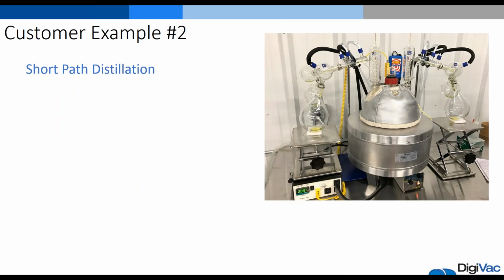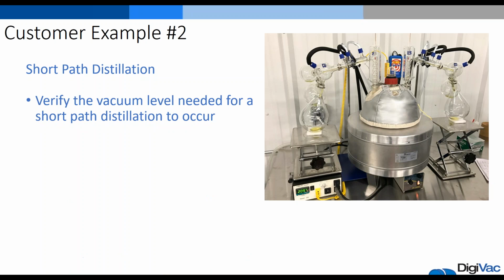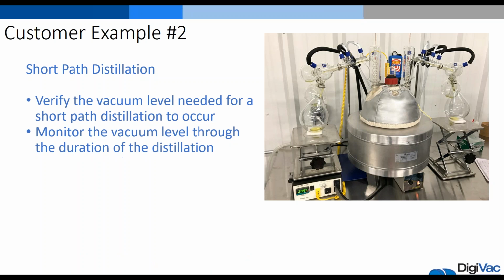Another customer example would be short path distillation, and the gauge can be used to verify that the vacuum is at a level needed for the short path distillation to occur, and you can monitor the vacuum level through the duration of the distillation. So you would use the gauge, if you can see in the image on the right, to sit there and monitor the pressure within the distillation process. And you can see when the pressure is rising and dropping to make sure it's at the appropriate level and not above or below what's needed.